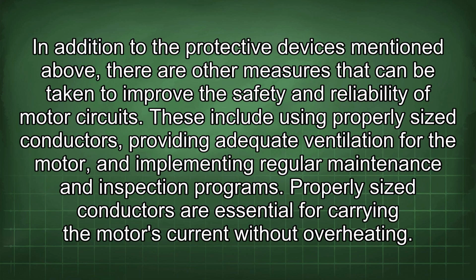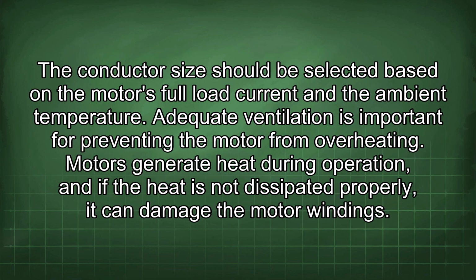In addition to the protective devices mentioned above, there are other measures that can be taken to improve the safety and reliability of motor circuits. These include using properly sized conductors, providing adequate ventilation for the motor, and implementing regular maintenance and inspection programs. Properly sized conductors are essential for carrying the motor's current without overheating. The conductor size should be selected based on the motor's full load current and the ambient temperature. Adequate ventilation is important for preventing the motor from overheating. Motors generate heat during operation, and if the heat is not dissipated properly, it can damage the motor windings.